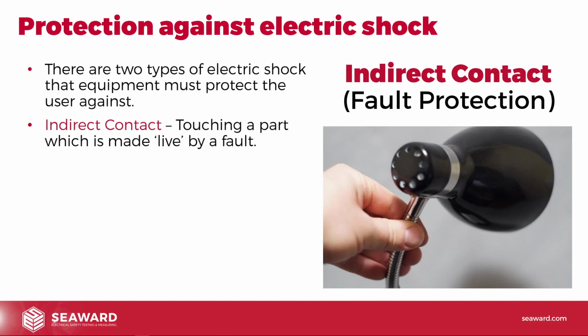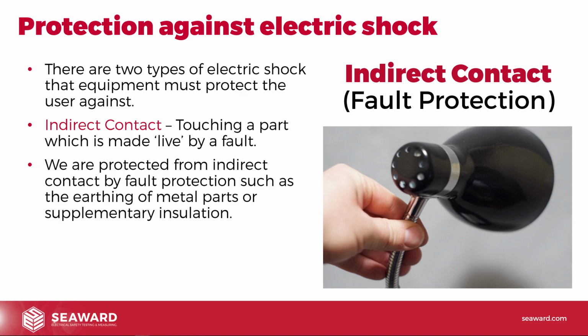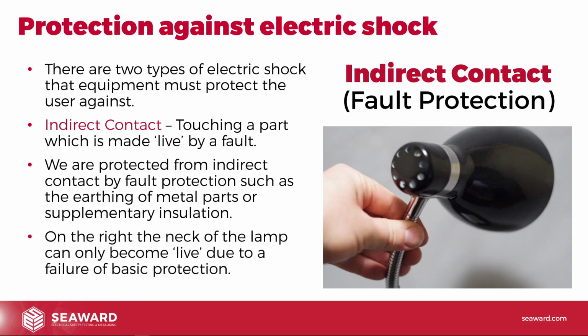Now, indirect contact is touching a part which is made live only by a fault. So these are things that shouldn't be live normally, but could become live if there was a fault. So we're protected from indirect contact by fault protection, such as the earthing of metal parts in Class 1 equipment or supplementary insulation in Class 2 equipment. On the right, the neck of the lamp can only become live due to a failure of basic protection. So if the basic insulation, you imagine in the neck of that light, there's two cables going up inside there, the line and neutral, they've got insulation. Now, if over time they get shorted out, they get frayed, the basic insulation around them has failed, in which case the body of the lamp has become live.